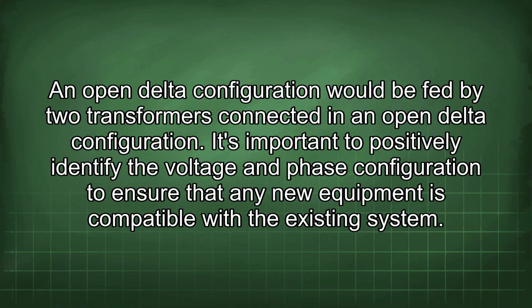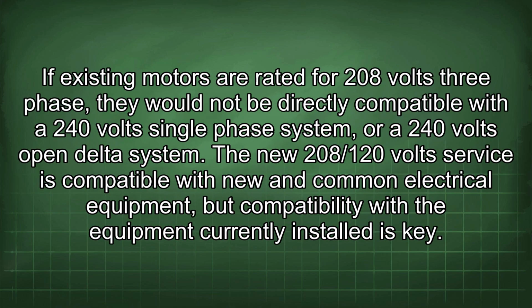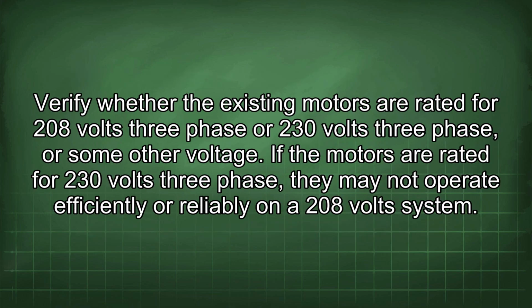It's important to positively identify the voltage and phase configuration to ensure that any new equipment is compatible with the existing system. If existing motors are rated for 208 volts three-phase, they would not be directly compatible with a 240 volts single-phase system or a 240 volts open delta system. The new 208/120 volts service is compatible with new and common electrical equipment, but compatibility with equipment currently installed is key. Verify whether the existing motors are rated for 208 volts three-phase or 230 volts three-phase or some other voltage.